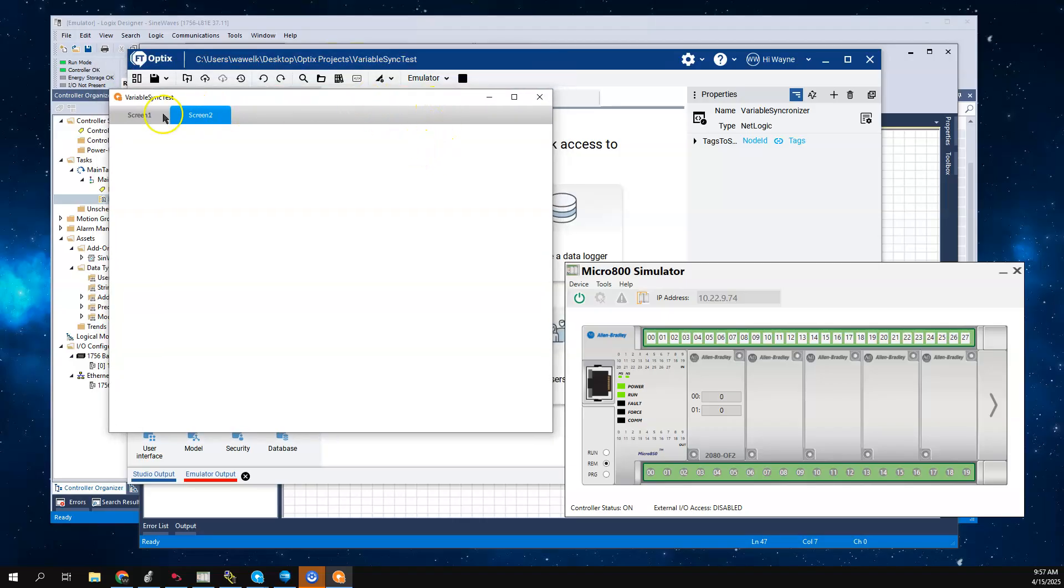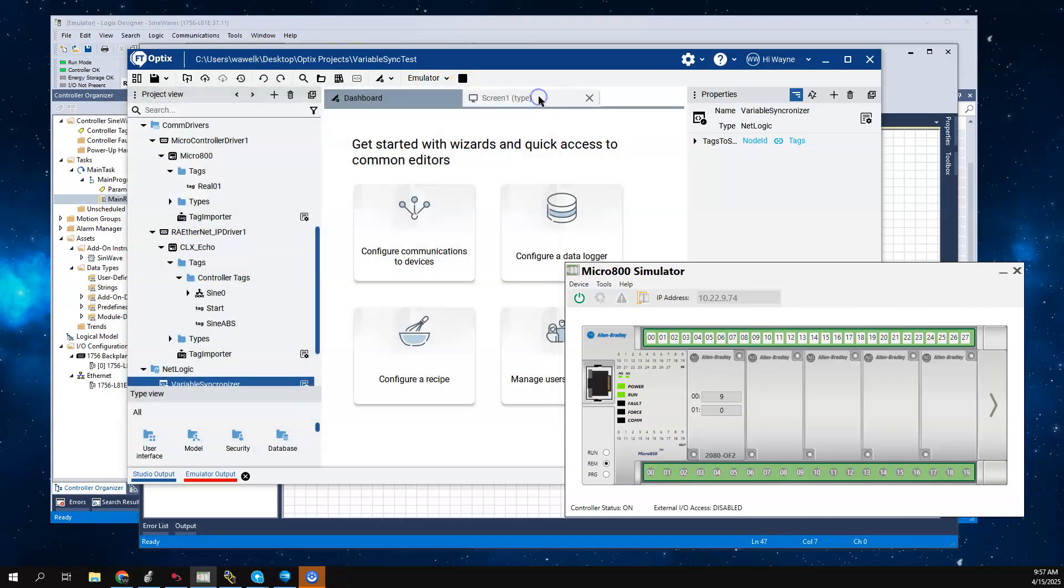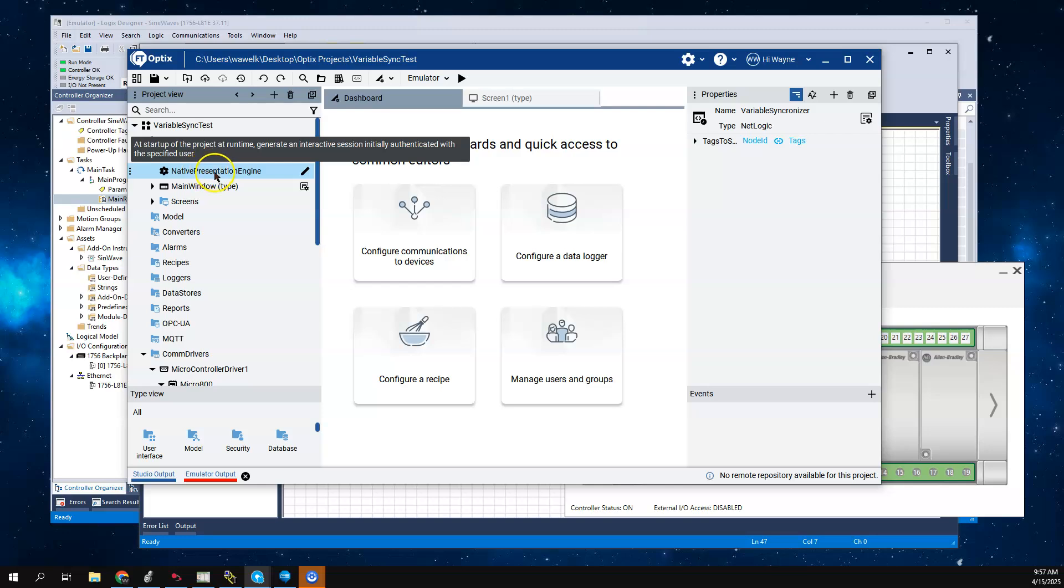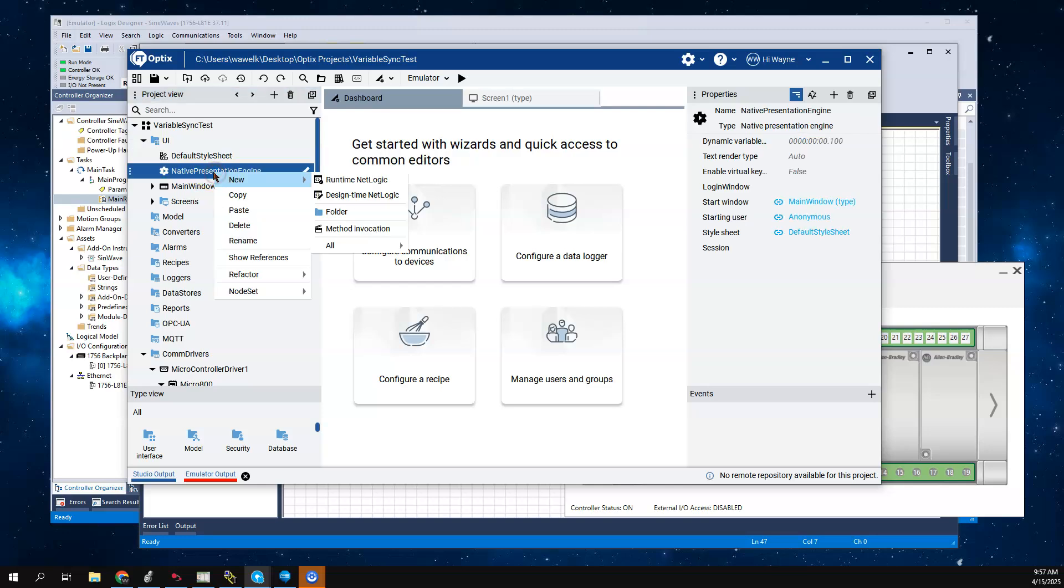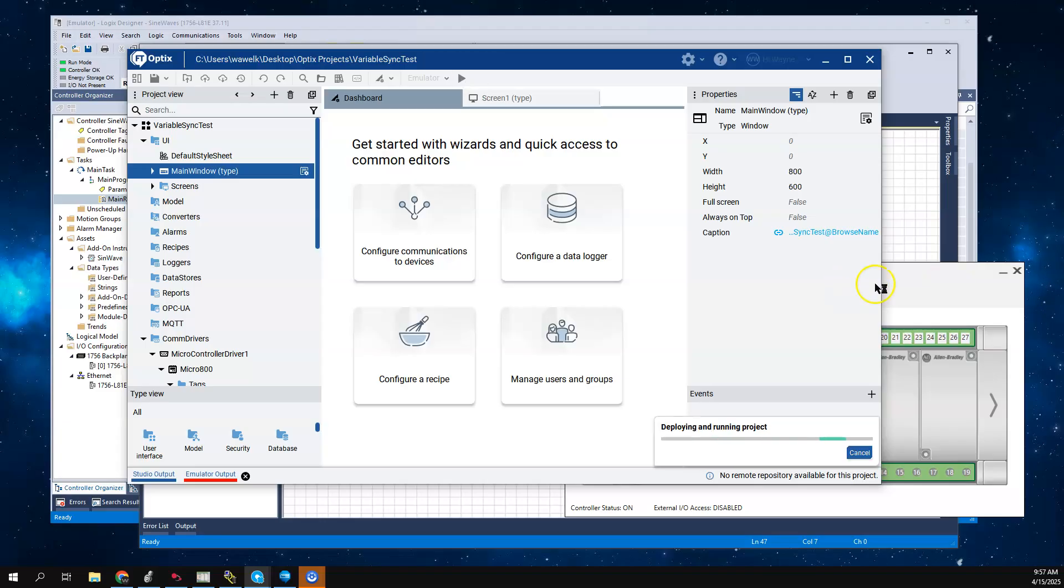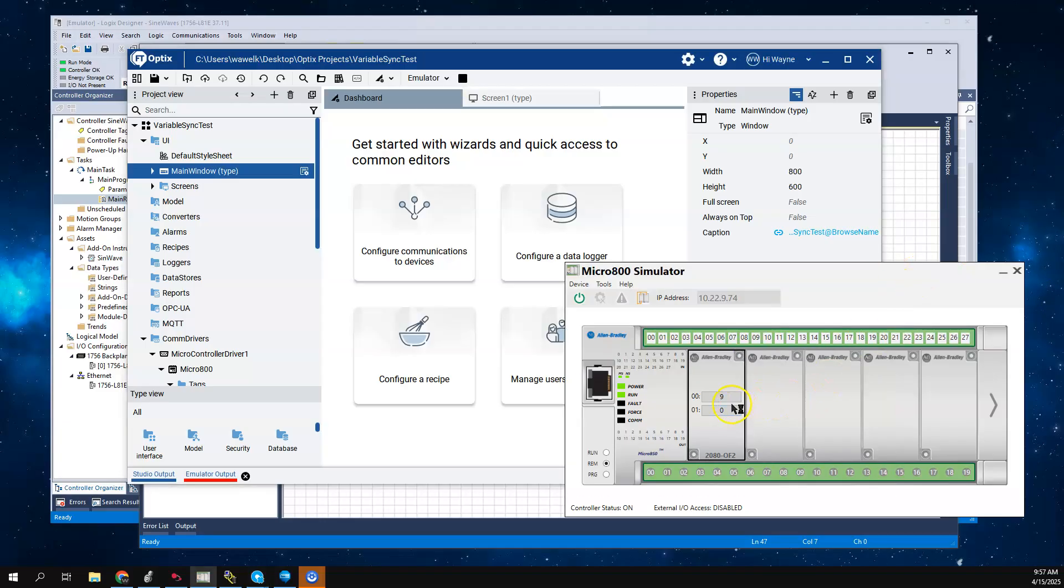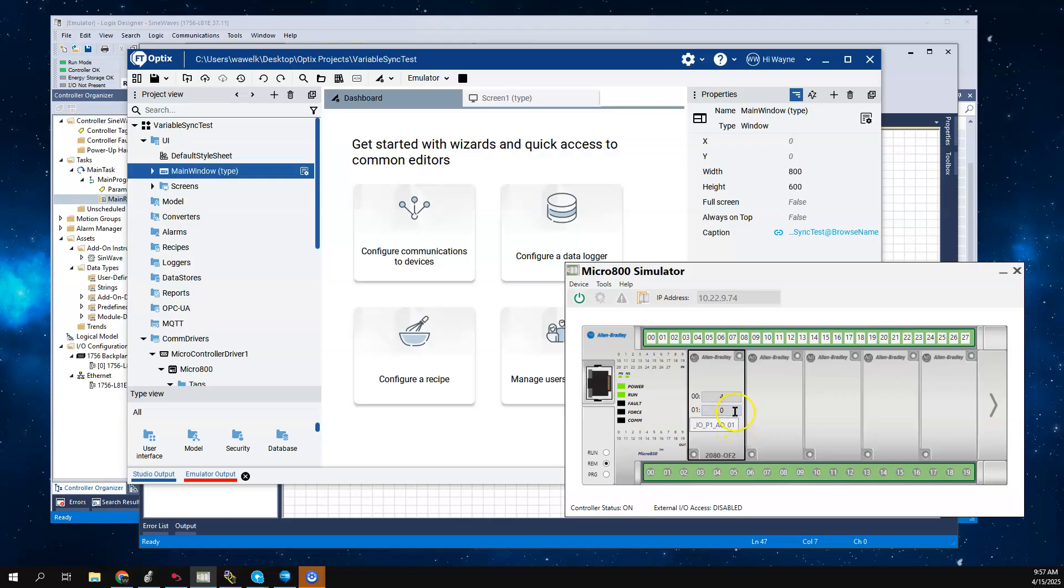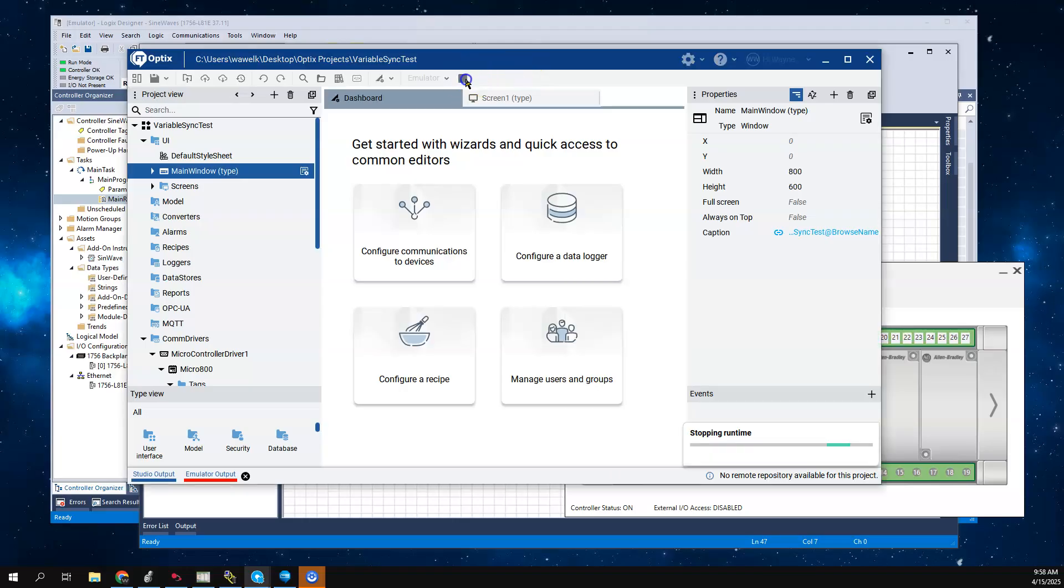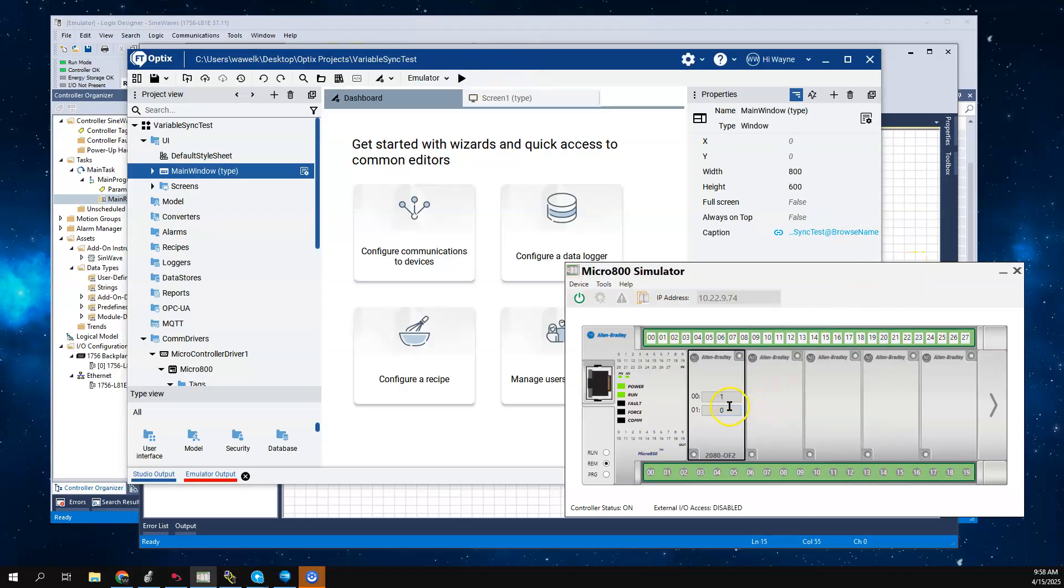We did say originally about the idea of being headless. To be a headless version of Optix, we wouldn't have a native presentation engine at all. If I go ahead and delete this native presentation engine to get rid of that altogether, now when I run the emulator there will be no screen to show. We can see once it gets running that now it's updating. Basically the ControlLogix tags are being passed right into the Micro 800. I don't have any HMI component here at all. It's acting completely as a headless gateway or Optix as a service.